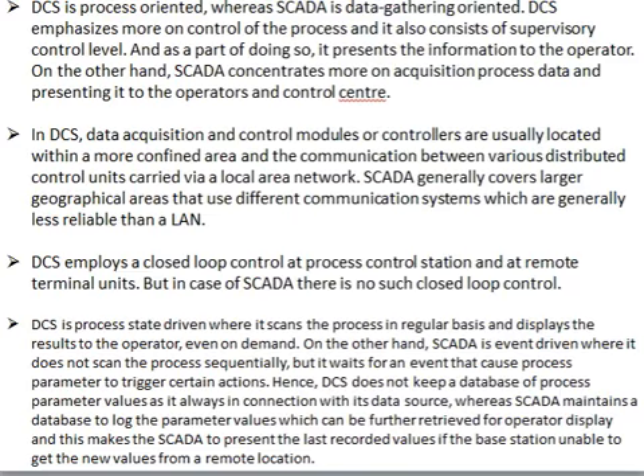DCS is process state-driven, where it scans the process on a regular basis and displays the results to the operator, even on demand. On the other hand, SCADA is event-driven, where it does not scan the process sequentially, but waits for an event that causes a process parameter to trigger certain actions. Hence, DCS does not keep a database of process parameter values as it is always in connection with its data source, whereas SCADA maintains a database to log the parameter values, which can be retrieved for operator display. This makes SCADA present the last recorded values if the base station is unable to get the new values from a remote location.